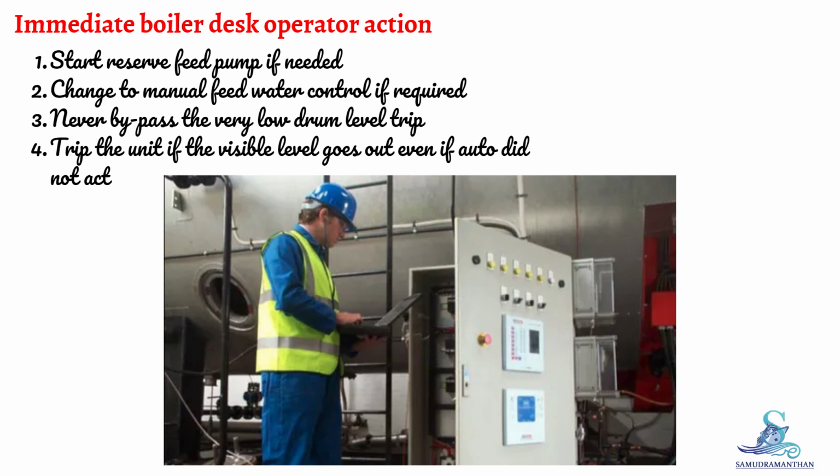Start reserve feed pump if needed. Change to manual feed water control if required. Never bypass the very low drum level trip. Trip the unit if the visible level goes out even if auto did not act.